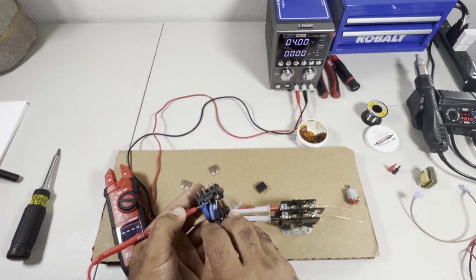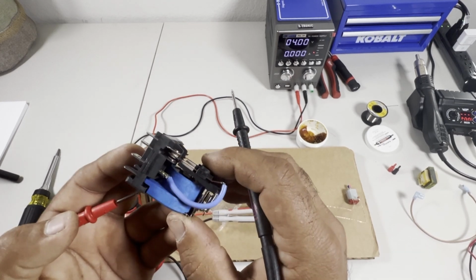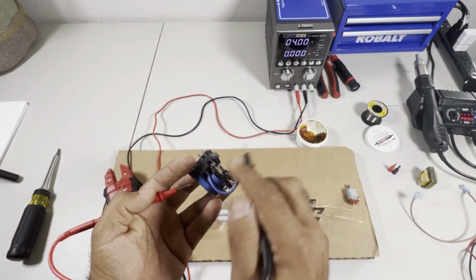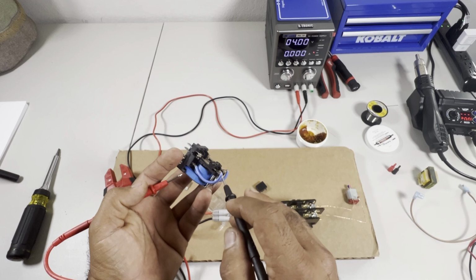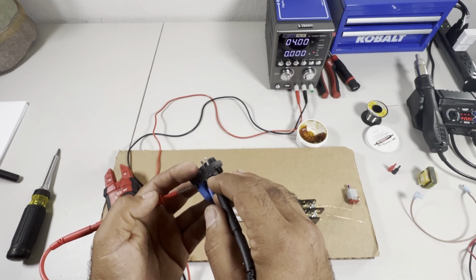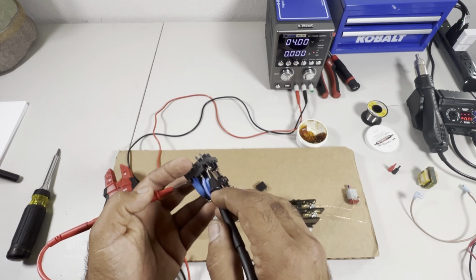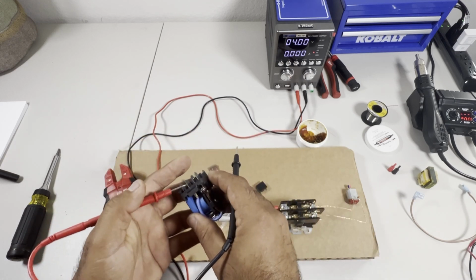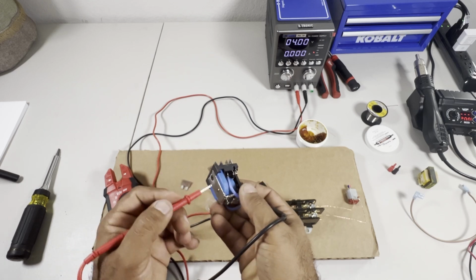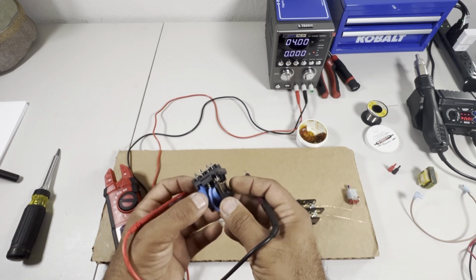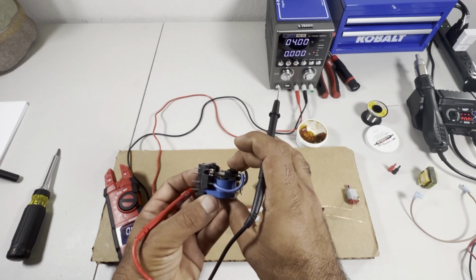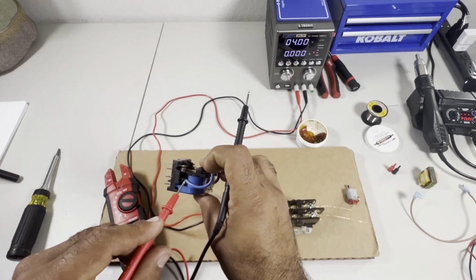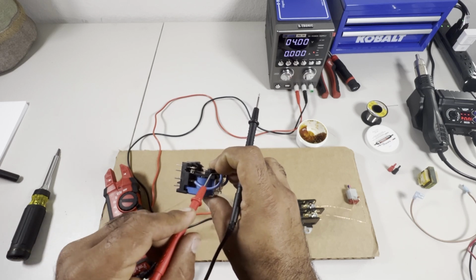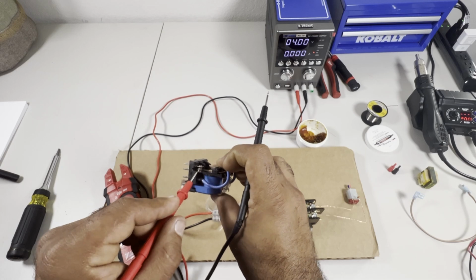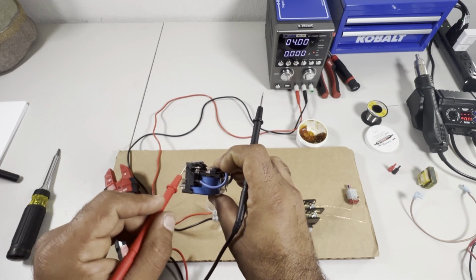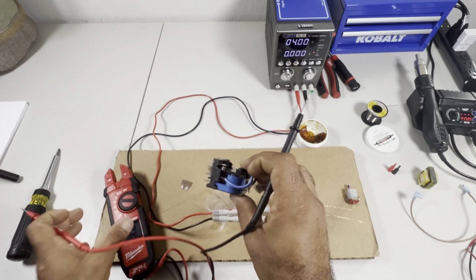And this one, you see there is a little bit of gap right there. You can see this one can go up and down. So electrons come in, they go all the way here. They can go easily to this point, but none of them can go here because there is a gap right here. As soon as you supply power to these two, this coil, this magnet, will energize and pull this one down really hard. And when it does that, it closes this to this terminal now, and the gap is up here right now. So now nothing can pass through that terminal.